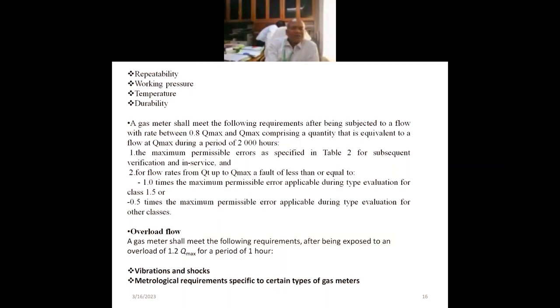And a gas meter shall meet the following requirements after being subjected to flow, with rate between 0.8 Q maximum and Q maximum, comprising a quantity that is equivalent to a flow at Q maximum during a period of 2000 hours. This is the durability condition. It should require, for the flow rates from QT up to Q maximum, a fault of less than or equal to 1.0 times the maximum permissible error applicable during the type evaluation for class 1.5, or 0.5 times.